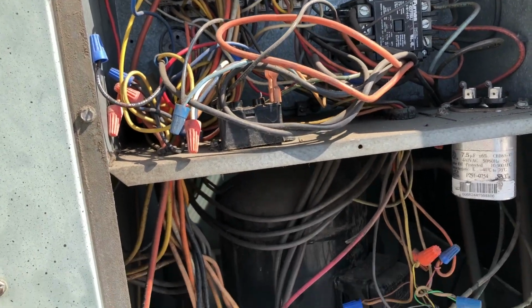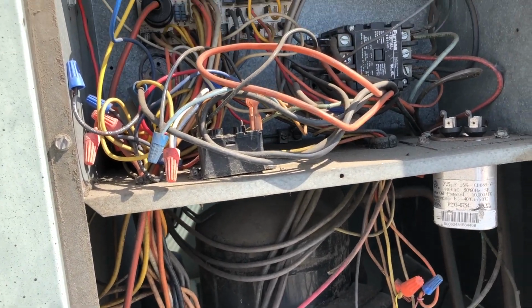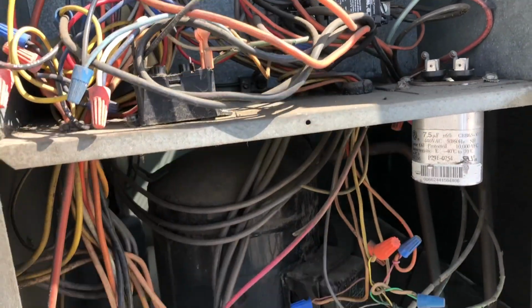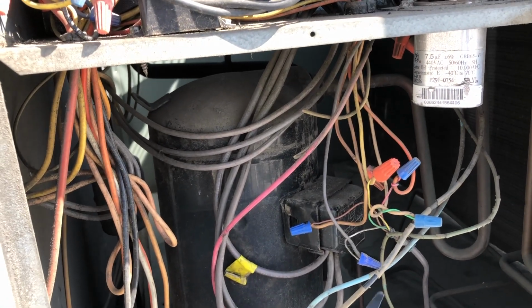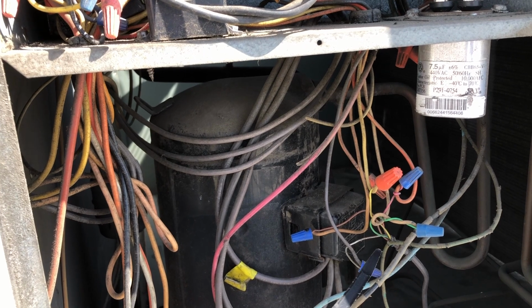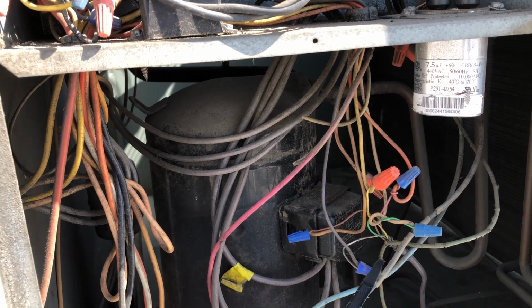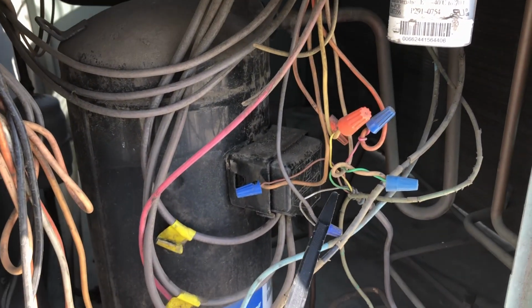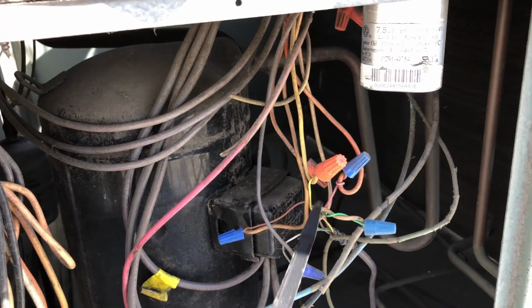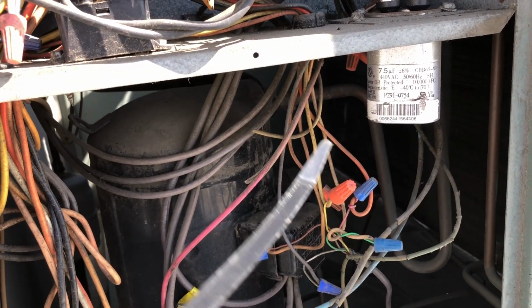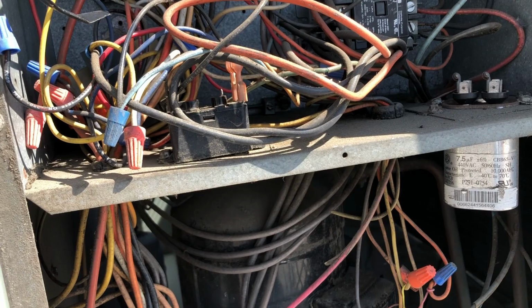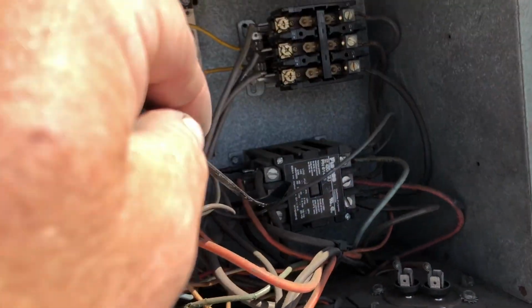So I'm looking at an old school hack job that I did. This unit has low voltage, from about 20 years ago. The thermostat wire gauge is too small, so it's getting low voltage, and it's burning up the contactor.